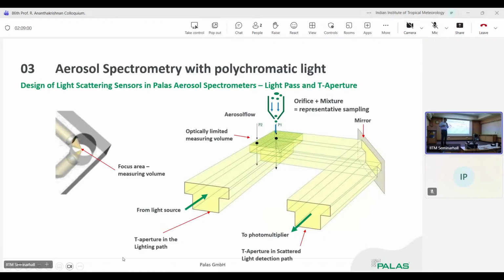But for high concentrations, we need a certain statistics. If we have a low concentration and a sensor used for very high concentrations, more than 1 million, then we have bad statistics in the lower range. So if you want to measure 100 or 10 particles per cubic centimeter, this is not possible, because there are not enough signals to determine the particle size distribution. This is how we do it: we enhance or decrease the area, and of course the optics are also modified so that they fit the analysis area of the light scattering.